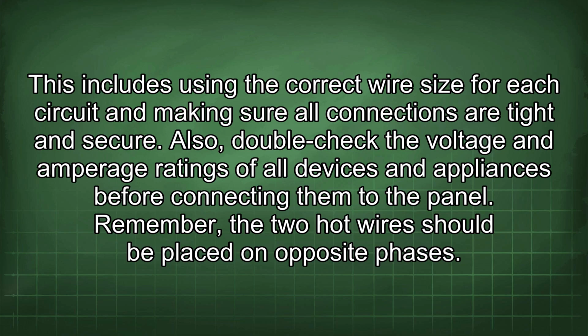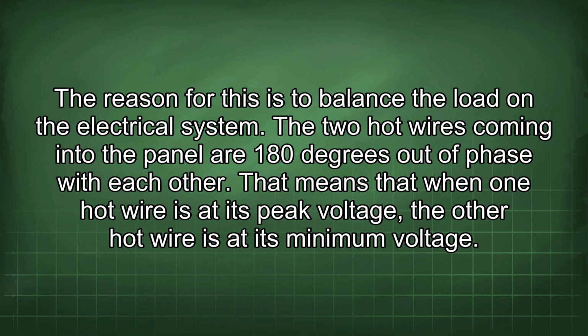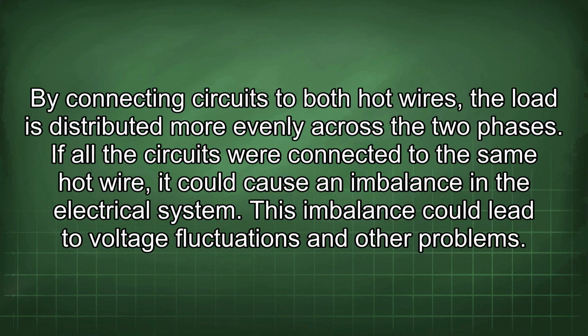Remember, the two hot wires should be placed on opposite phases. The reason for this is to balance the load in the electrical system. The two hot wires coming into the panel are 180 degrees out of phase with each other. That means that when one hot wire is at its peak voltage, the other hot wire is at its minimum voltage. By connecting circuits to both hot wires, the load is distributed more evenly across the two phases. If all the circuits were connected to the same hot wire, it could cause an imbalance in the electrical system. This imbalance could lead to voltage fluctuations and other problems.